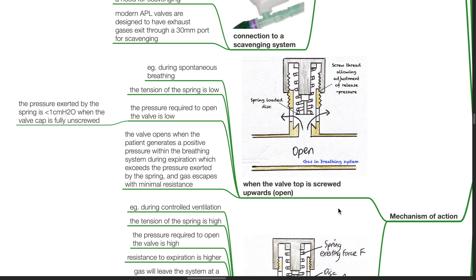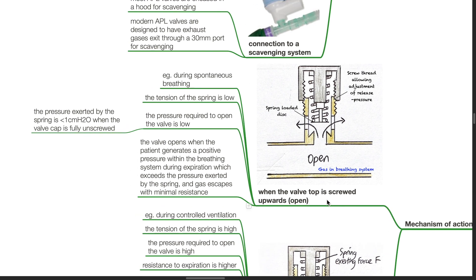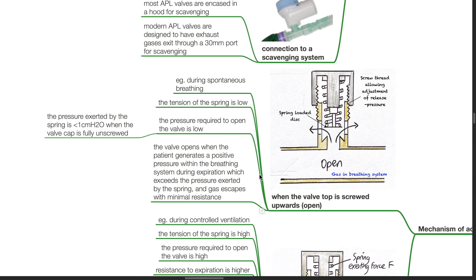Mechanism of action. When the valve top is screwed upwards, for example during spontaneous breathing, the tension of the spring is low. The pressure required to open the valve is low. The pressure exerted by the spring is less than 1 CMH2O when the valve cap is fully unscrewed. The valve opens when the patient generates a positive pressure within the breathing system during expiration, which exceeds the pressure exerted by the spring, and gas escapes with minimal resistance.